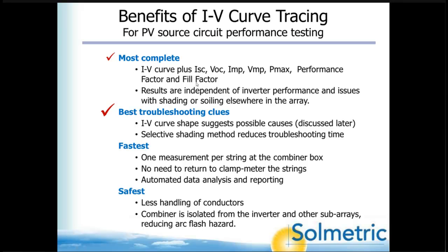And another nice thing about it is that the results are independent of the inverter performance and any issues with shading or soiling elsewhere in the array. And the reason for that is because the combiner is taken offline, the fuses are lifted, and the individual strings are measured, isolated from everything else. So you find out what the actual string-specific max power value is.